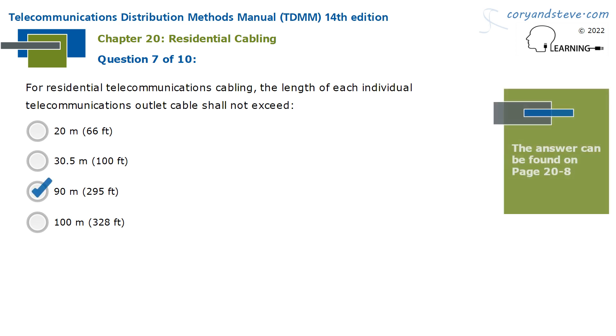For residential telecommunications cabling, the length of each individual telecommunications outlet cable shall not exceed 90 meters, or 295 feet.